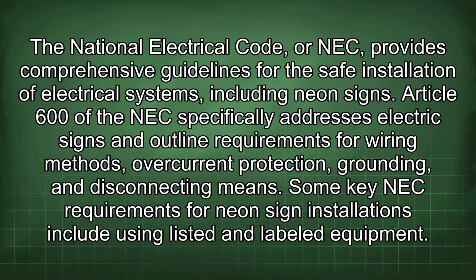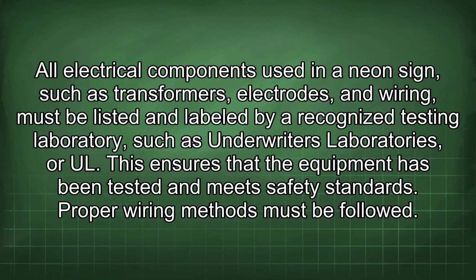The National Electrical Code, or NEC, provides comprehensive guidelines for the safe installation of electrical systems, including neon signs. Article 600 of the NEC specifically addresses electric signs and outline requirements for wiring methods, overcurrent protection, grounding, and disconnecting means. Some key NEC requirements for neon sign installations include using listed and labeled equipment. All electrical components used in a neon sign, such as transformers, electrodes, and wiring, must be listed and labeled by a recognized testing laboratory, such as Underwriters Laboratories, or UL. This ensures that the equipment has been tested and meets safety standards.